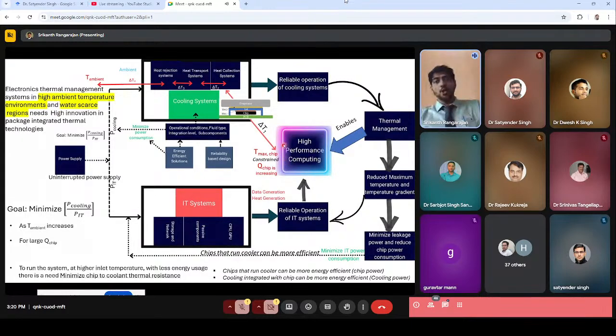And if you want to remove a kilowatt of heat from one chip, you can calculate the available resistance. For a 30 degree Celsius delta T removing 1 kilowatt of heat, the thermal resistance is 0.03.